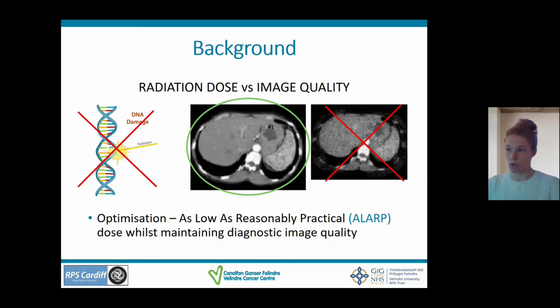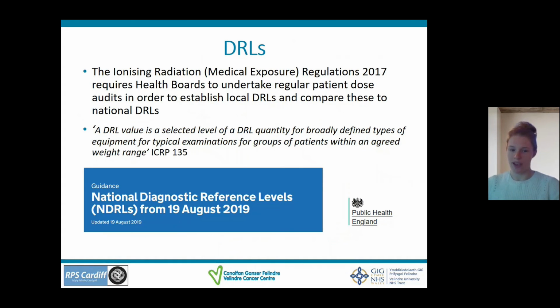Now, diagnostic reference levels, or DRLs for short, are used to track dose, and we do this through dose audits. So we look at all the medical imaging scans that have been performed, for example chest X-rays at a certain health board for a few months, and we say, okay, what is the average dose here? What is the dose that we imagine a standard size patient to get from this scan? And we do some statistics on this, and we come up with our diagnostic reference levels, our DRLs. Now, all other scans are compared to this diagnostic reference level, so it is important that this level is right, and there are ways that we can do this.